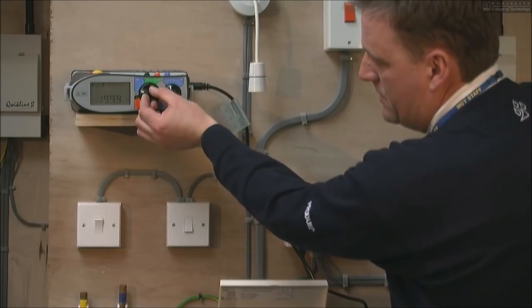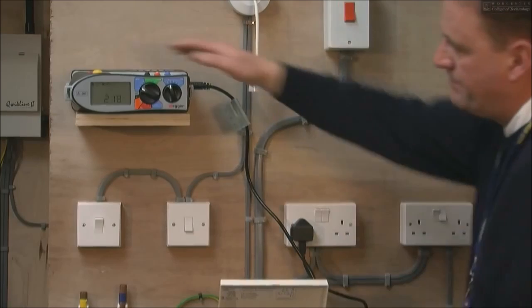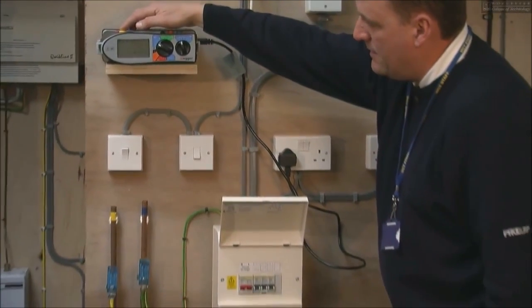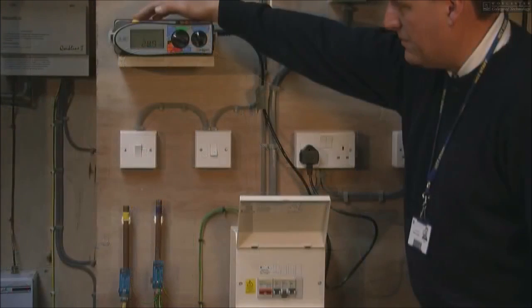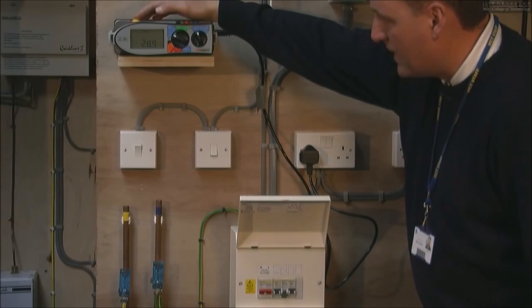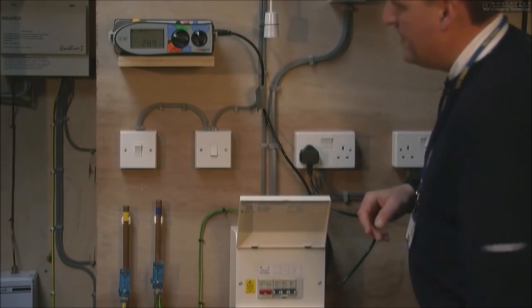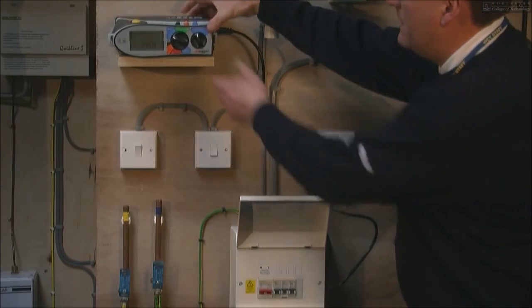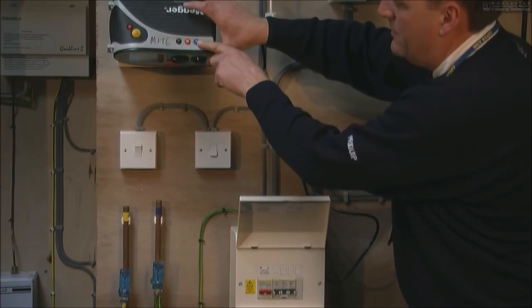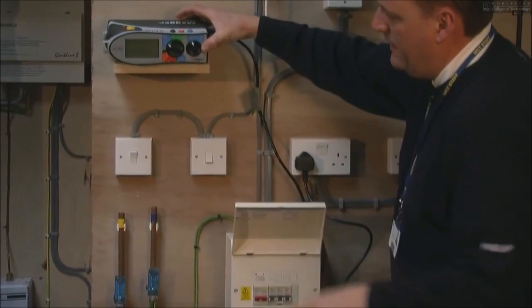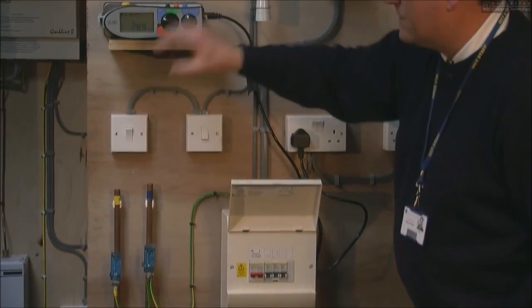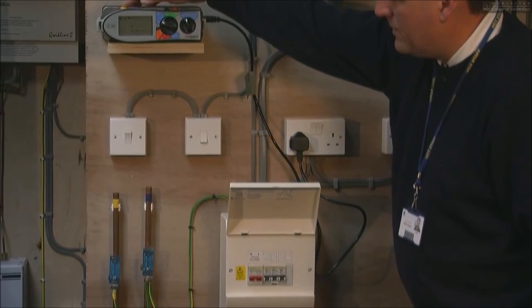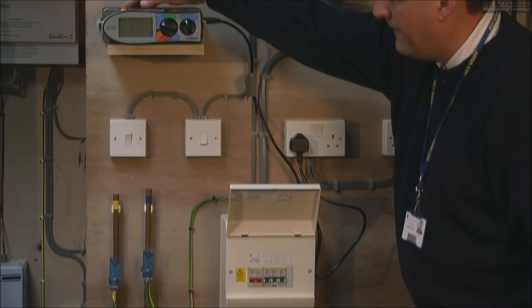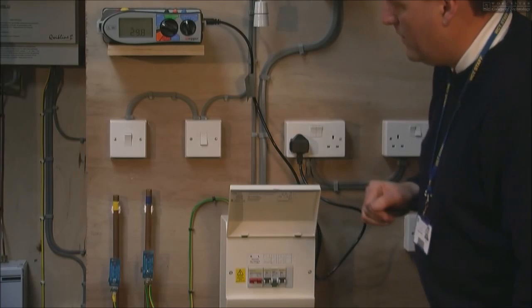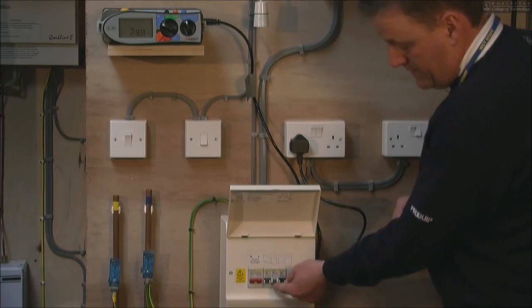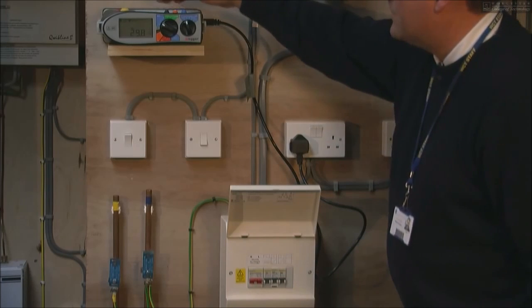So then move the tester across to the ×1, and this time when we press the button, and we have 28.9 milliseconds. We reset the RCD. On the top of the tester we have a little button here from 0 to 180. We press that button. That now sets it onto the negative side of the wave cycle. We press the button and we're at 29.8 milliseconds. Again, compare those readings to the relevant regulations.